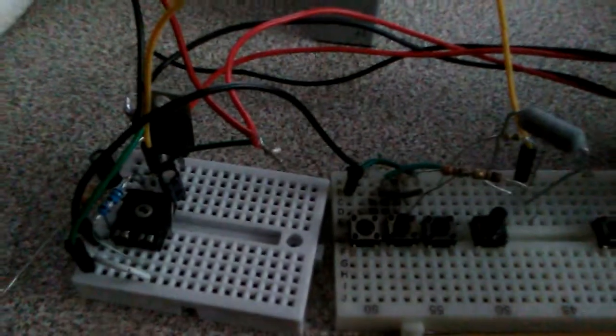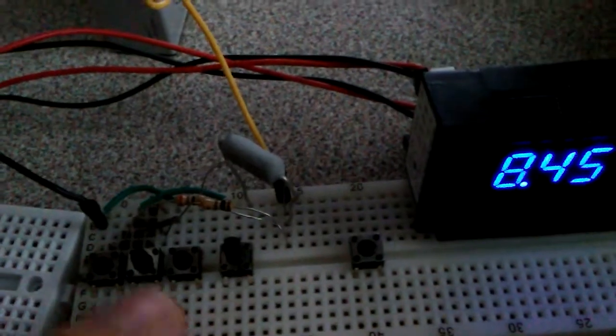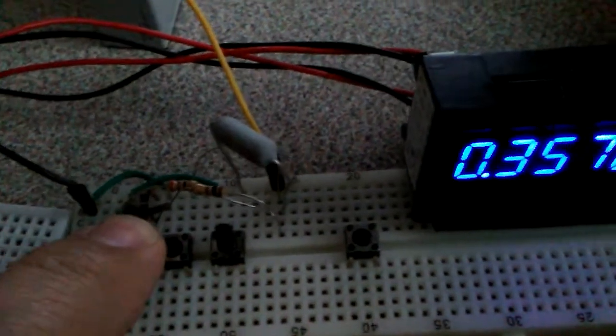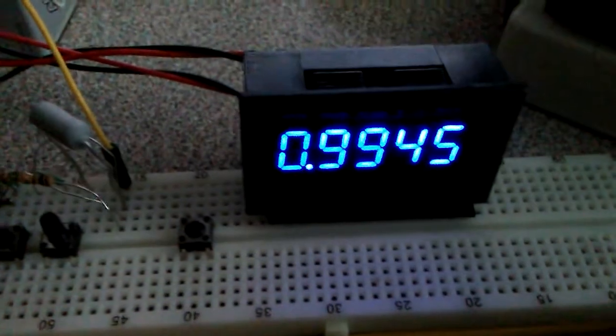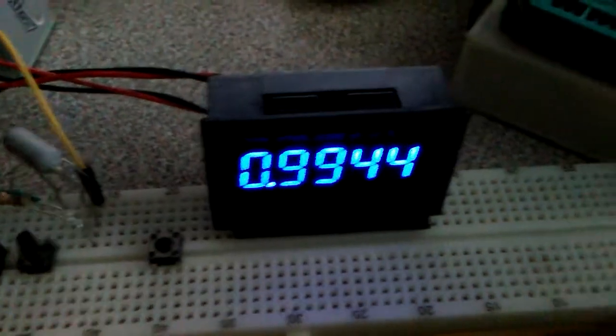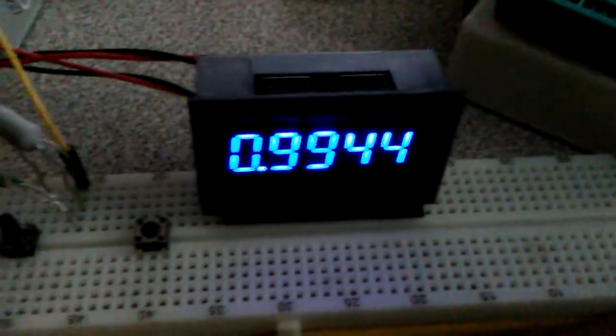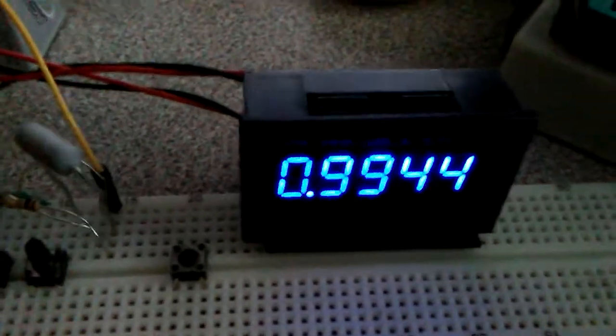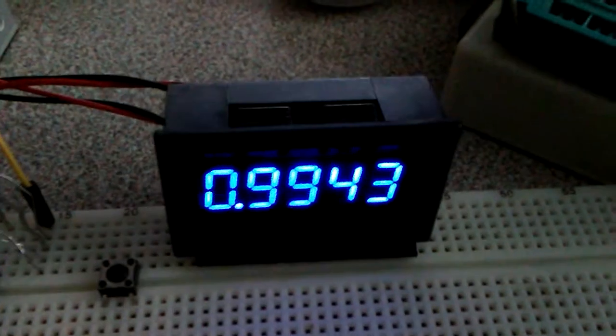To test and calibrate the project, first connect 100 milliohm resistors to the project like this. Connect the 100 milliohm to the device and adjust for alignment until it reads 99.99.